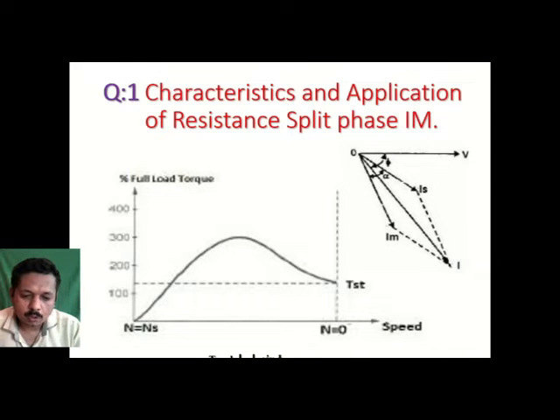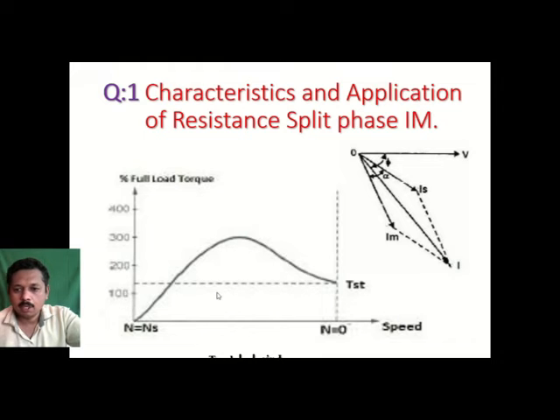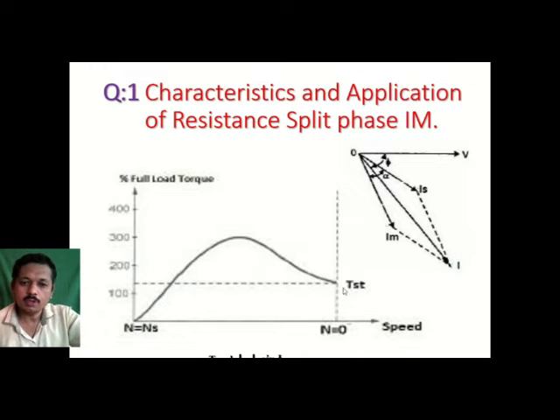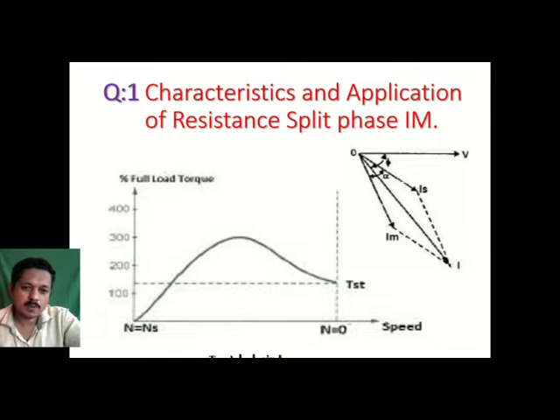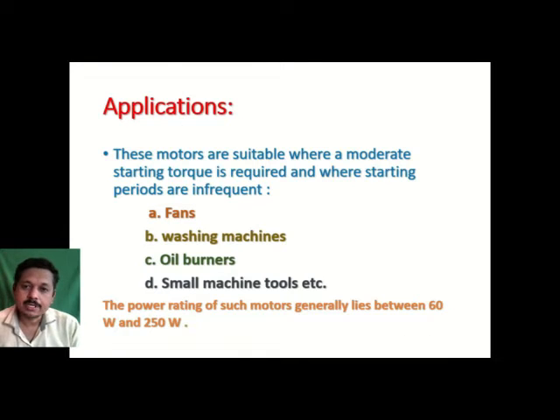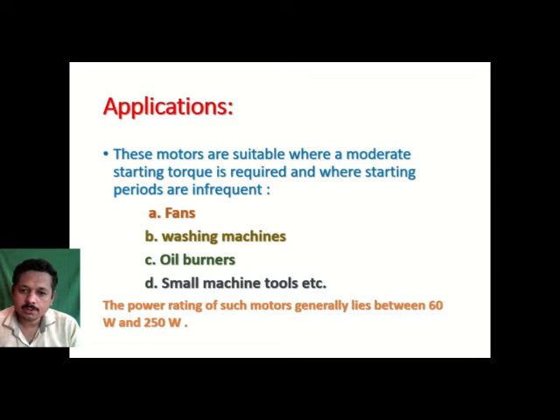This is a constant speed motor. As observed in the characteristics, it can consistently run at more than 100% torque, making it suitable for constant speed applications. However, the operation should not be frequent — due to its starting time limitation, we use this motor where operation is very infrequent and starting torque requirement is moderate, not very high. Applications include fans, washing machines, oil burners, small machine tools, etc.